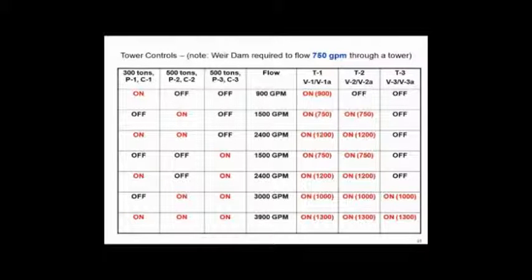Now I've got T1, T2, T3 towers available. And I've got the shutoff valves, T1, T1A, T2, T2A on each one. Now if I went ahead and valved off tower 2 and tower 3, they're off. My flow rate through tower 1 would be what? 900 GPM. Is that acceptable? Absolutely. The minimum flow rate is what? 750. The max flow rate is what? 1500. That's an acceptable operating condition. That's fine. No problems. No dry air disease. Great. We've got one fixed.